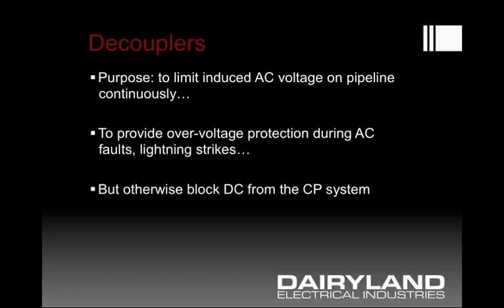The decoupler's purpose in the end is to limit the induced AC voltage on the pipe continuously, and provide overvoltage protection should there be an abnormal condition such as an AC fault or lightning strike. But under normal conditions it should block CP current, which is DC.